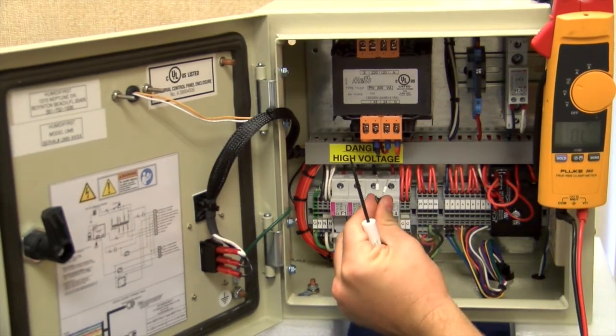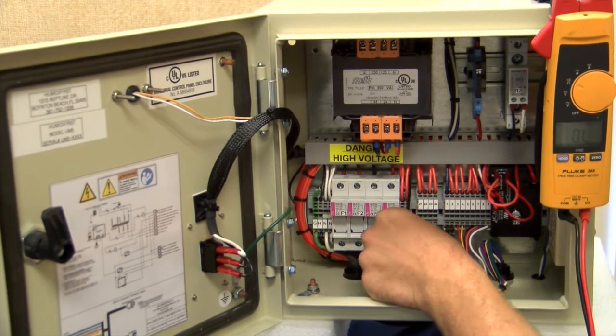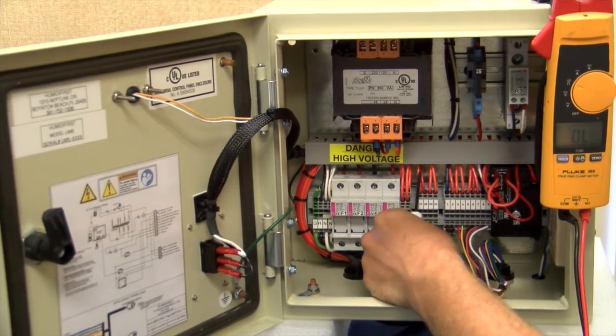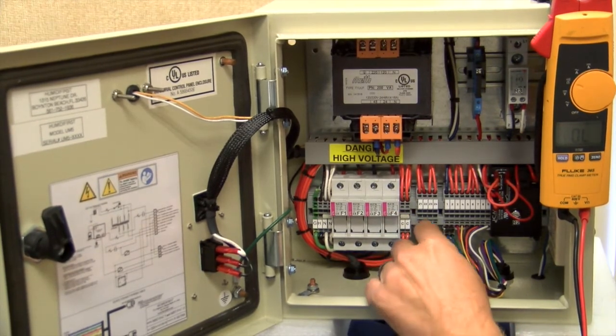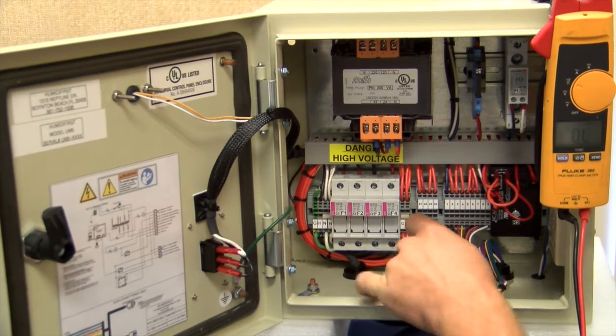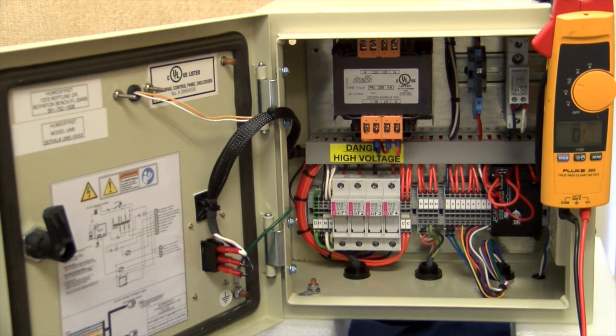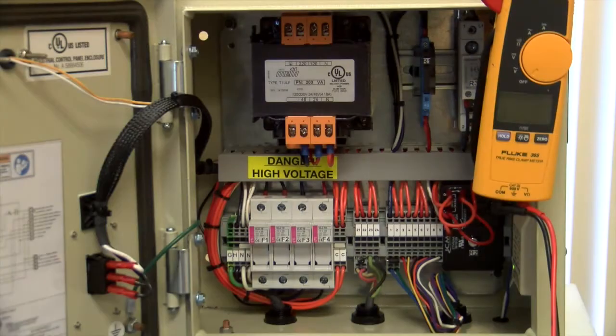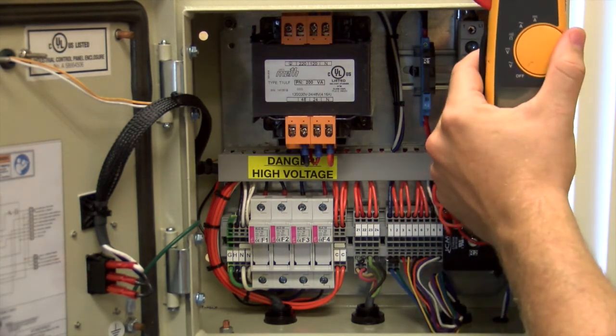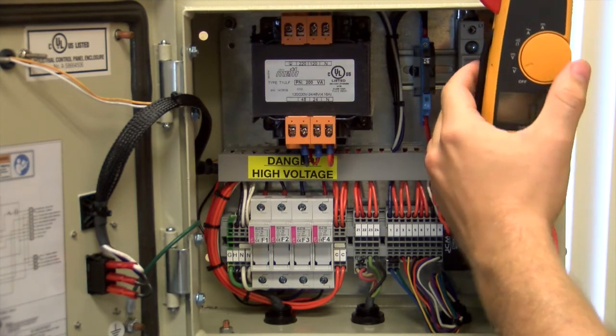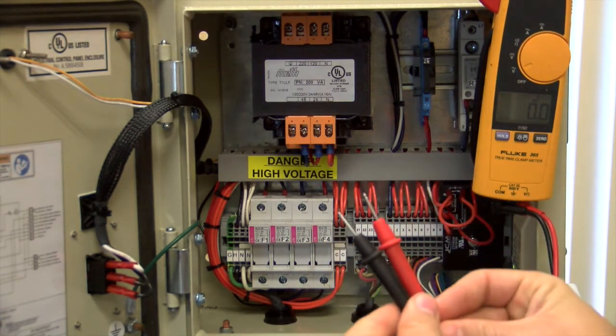To replace the surge arrestor, simply take it, place it in the two holes, take your Tech screwdriver, and push in. You have just replaced your surge arrestor. After making sure all of the fuses and surge arresters are working properly, we're then going to check our voltage across our transformer. In order to do that, we'll take our voltmeter and turn it to measure voltage, AC, not DC, and then we're going to measure across.